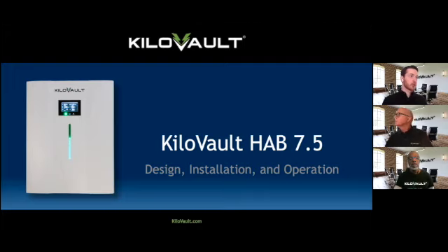I see a couple questions from Howie Michelson about the charge rate. You might have hopped on a little bit late. It was one of the first slides we went over. The maximum allowable charge rate is roughly a C1, and discharge rate is roughly a C1. To get the best lifespan out of the battery, it works out to about a C2.5, or even a C3, about a 50 amp max recommended charge rate.